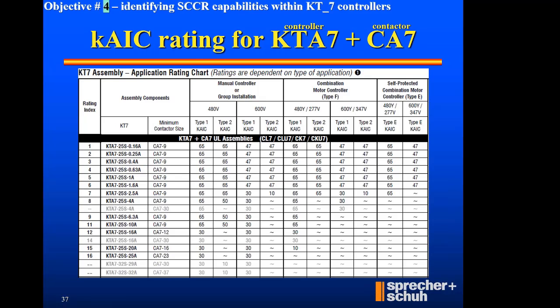Okay, well, that was controller only. What if I wanted to add a contactor because I needed to send it a signal remotely? Now these two components have been tested in coordination with each other. So now I've got a KAIC table that not only gives me my motor controller, but it gives me the minimum contactor size that's necessary to meet the approval.